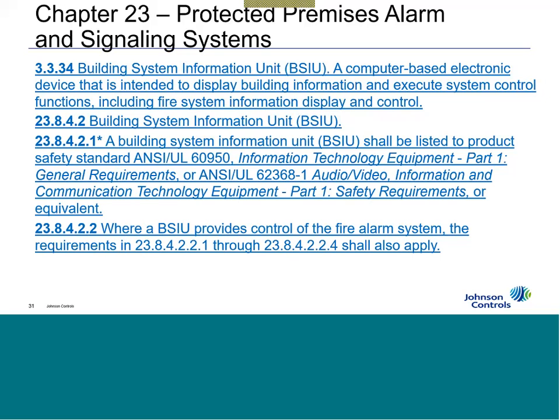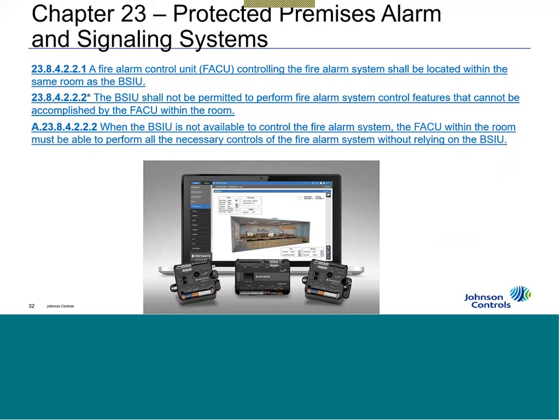The last part here, 23.8.4.2.2, where a BSIU provides control of the fire alarm system. Oh, there are some caveats you have to adhere to. A fire alarm control unit controlling the fire alarm system shall be located within the same room as the BSIU. What's always been the pushback on using off-the-shelf computers? Well, if that computer dies, locks up, doesn't work any longer, what do I do? So what they're saying is you need to be able to get up out of your chair if the computer dies, walk across the room, go to the fire alarm control unit on the wall, and whatever you were doing at that BSIU, I've got to be able to do with that fire alarm system.